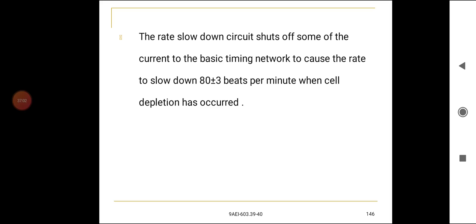There is a special circuit called the voltage monitor, which senses cell depletion and signals the rate slow down circuit and energy compensation circuit of the event. The rate slow down circuit shunts some of the current from the basic timing network to cause the rate to slow down to 80 plus or minus 3 beats per minute when cell depletion has occurred. The energy compensation circuit produces an increase in the pulse duration as the battery voltage decreases, to maintain constant stimulation energy to the heart.